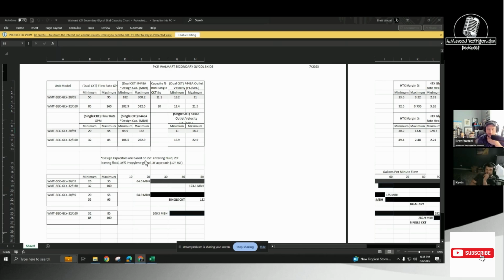This is funny though. Remember we were just looking at the sequence of operation. That was one of the first things we looked at, and it said 15 degrees to maintain 20, right? Yep. And this is saying designs are based on 27-degree entering fluid with 20-degree leaving fluid. But no, that's just return to supply. Yeah, that's just return to supply. But they say right here a 3-degree approach. That wasn't a 3-degree approach that they had earlier. That's what I'm noticing. I'm noticing that there's a conflict in what it's saying here.